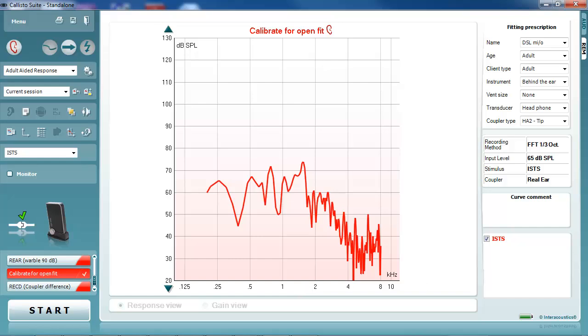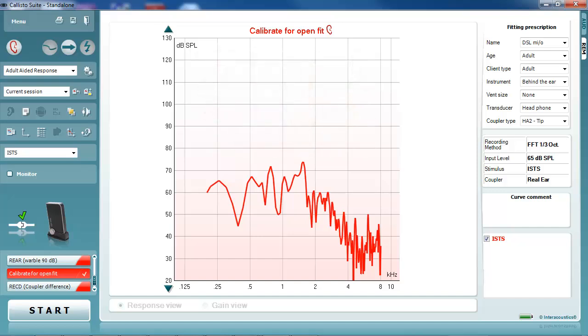It is important, however, to ensure that the patient maintains their position for the duration of the test, as stimulus corrections for patient movement will now not be performed by the software.